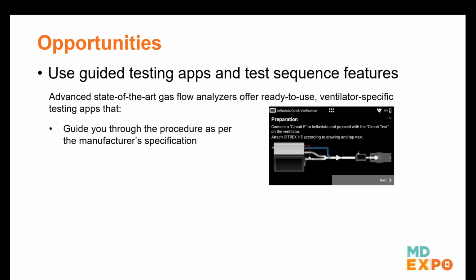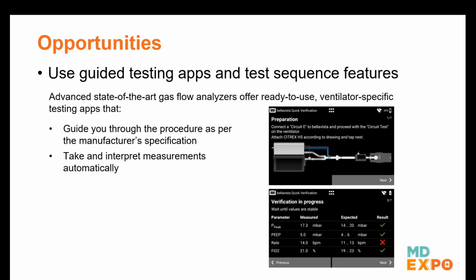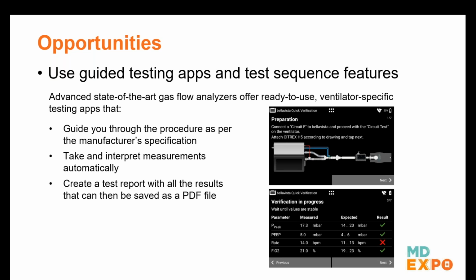So they show you how to set up the test setup with your device that you're using. They take the measurements automatically. They calculate the valid ranges based on the measurement, and they can give you pass-fail results right there on the screen, because it's all known, because the service manual procedure is programmed into an application running on the device. And the nice thing is it saves all these measurements and can then create a test report for you with all the results.